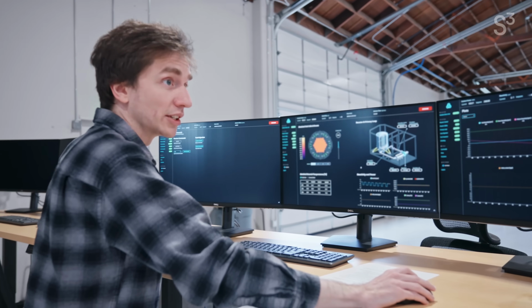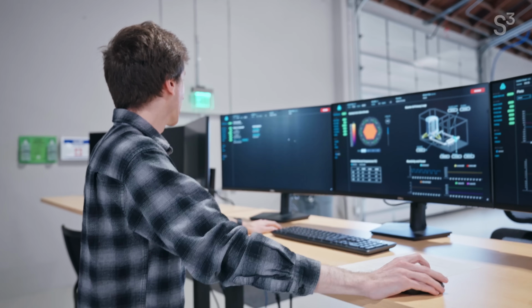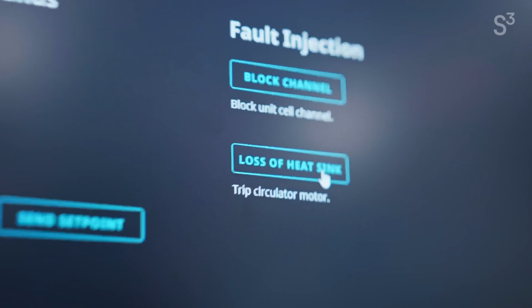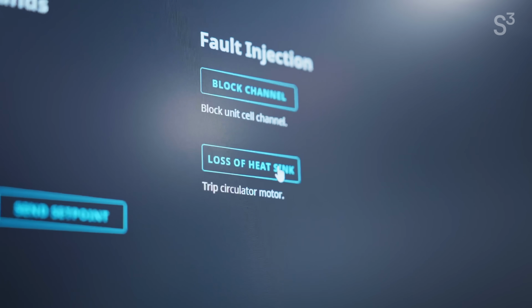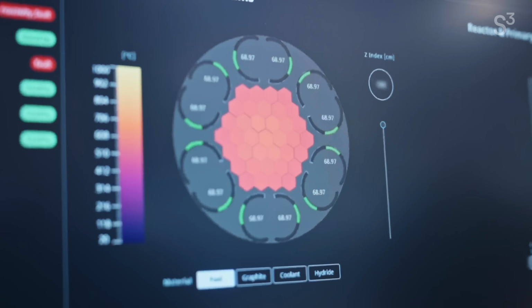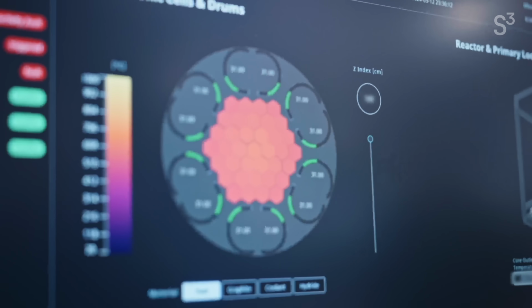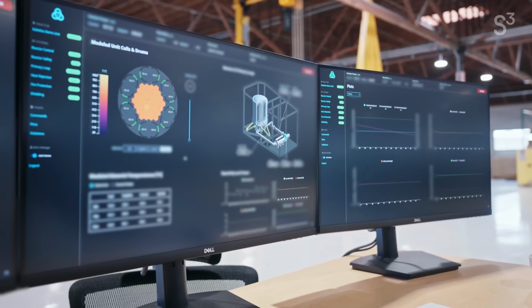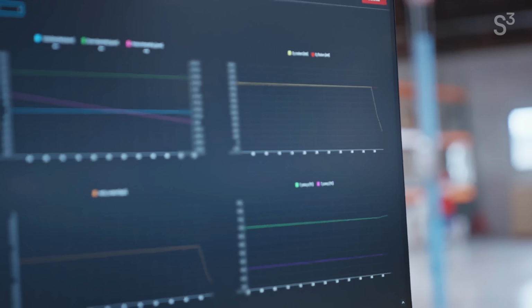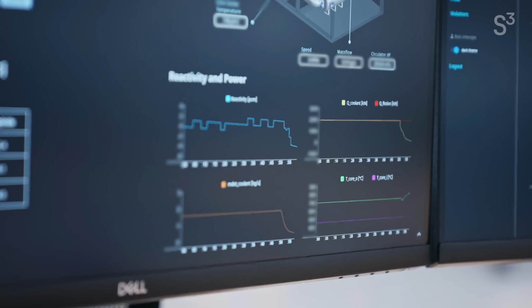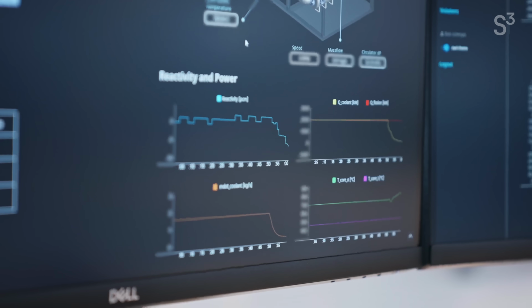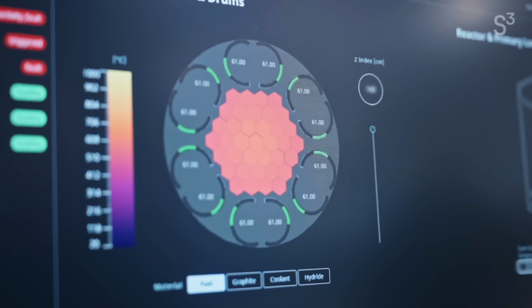One interesting thing we can do with the system is introduce system failures, where we can cause the heat sink, the primary motor that pushes helium through the reactor, to fail. So we click a button here, it commands it to go into a failed state, and we'll see the mass flow of the pump drop to zero, and the reactor start to heat up as a result. Once it does this, it triggers a fault condition, and the reactor starts trying to save itself.